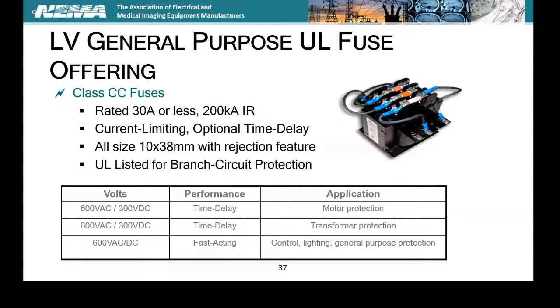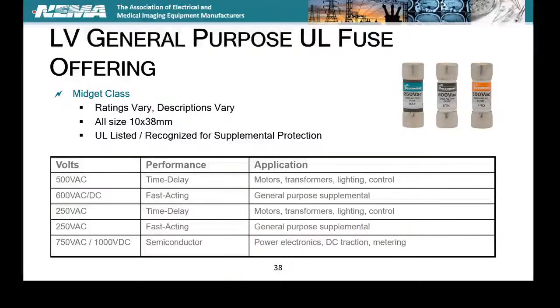Yeah, you'll see. What I like about this slide is it shows you the general applications on the right. You'll notice that anytime you see a time delay, you're going to see things like motors and transformers. You can also use time delay on non-inrush types of loads, but I could argue that there's some inrush on lighting too, especially the new lighting we've got these days. But in any case, you're fast acting.